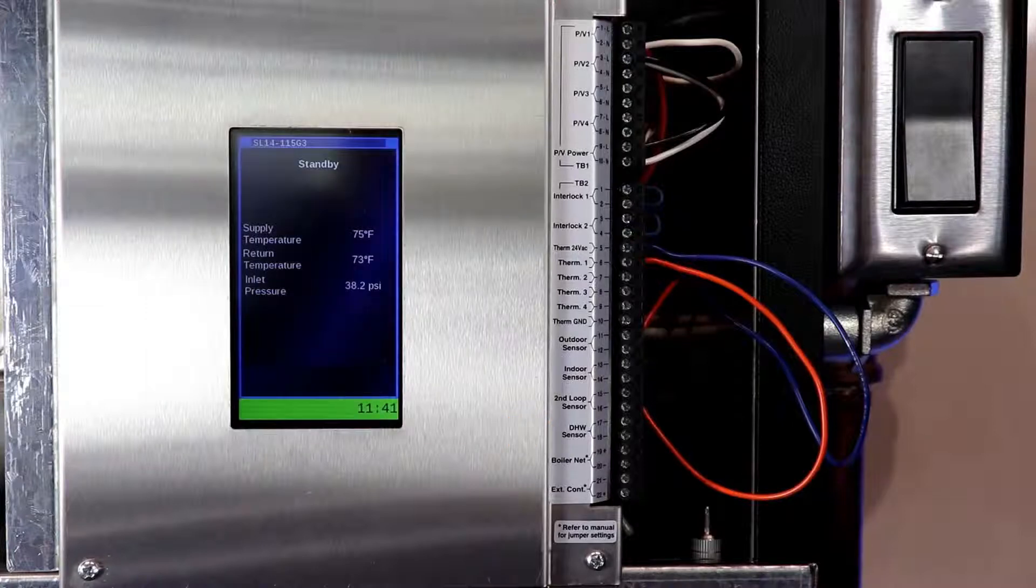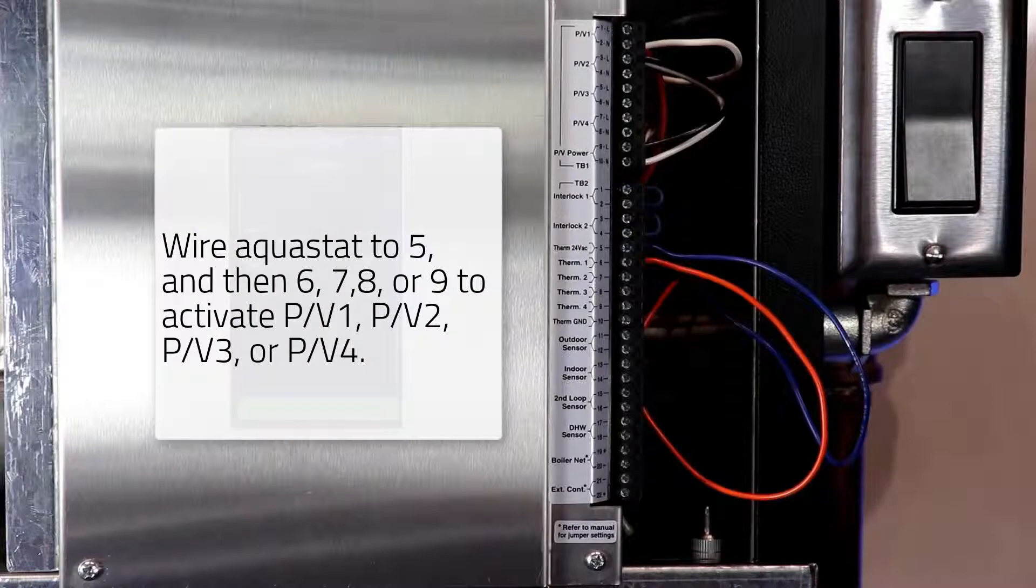If you are using an aquastat for your domestic call for heat, that will be wired into number 5 and the corresponding number 6, 7, 8, or 9, depending on the pump that you have wired to the TB1 terminal.